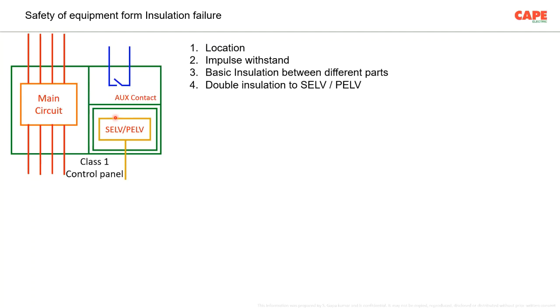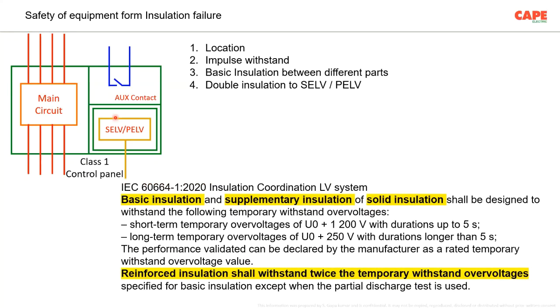While installing this particular panel or while designing the electrical panel, the panel manufacturer must understand and look into the standards about the location where the panel is going to be installed, about the impulse withstand of that particular location, basic insulation between different parts, the requirement of basic insulation, double insulation for SELV and PELV. You must understand these requirements and make the panel in such a way that it is satisfying the overall requirement.